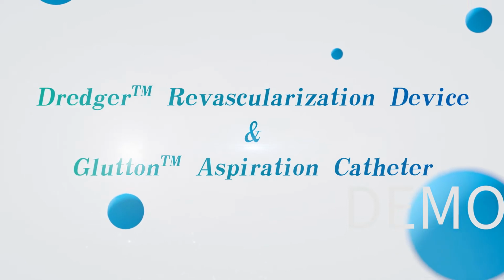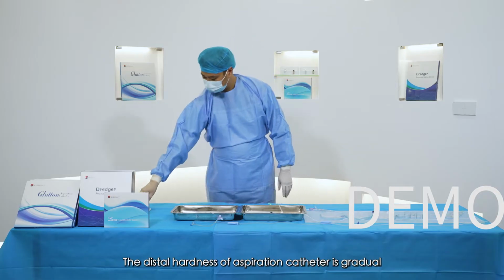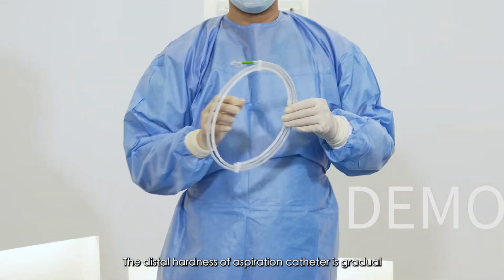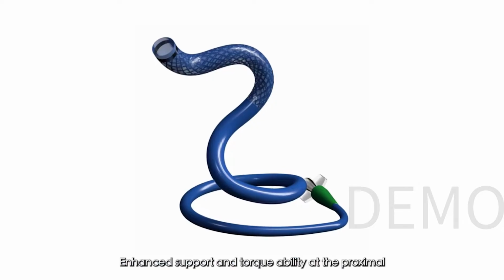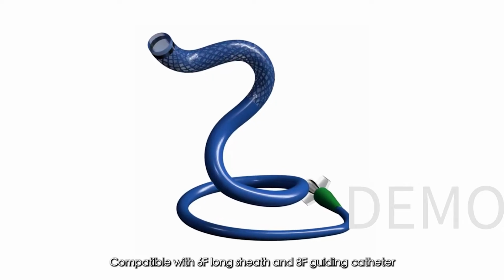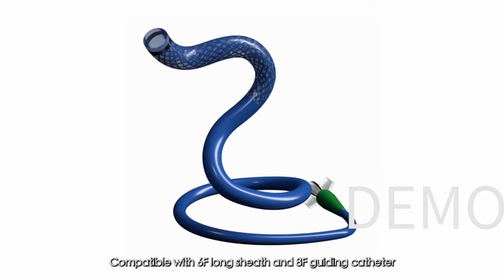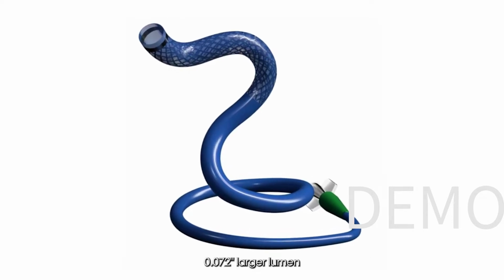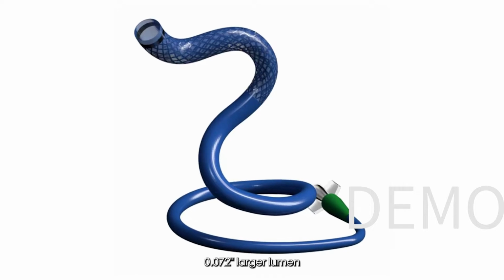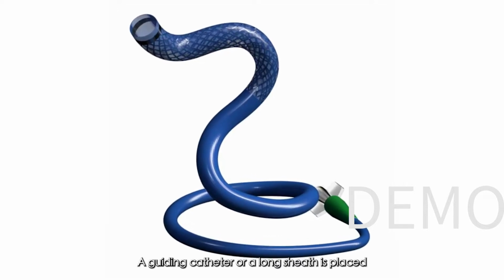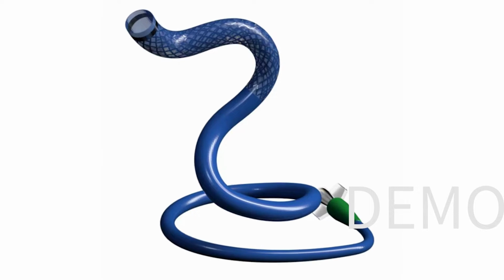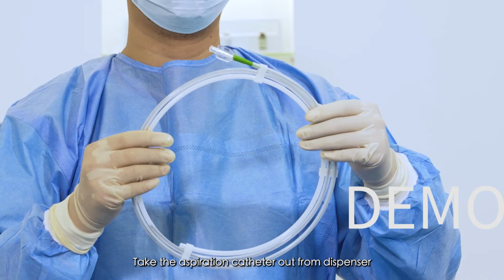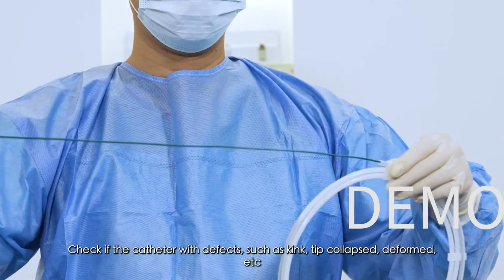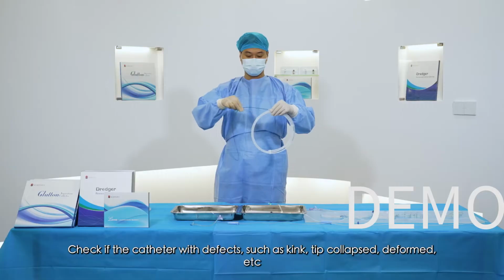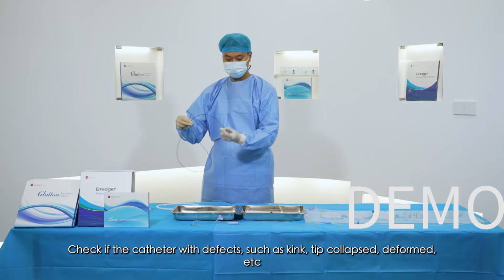The distal hardness of the aspiration catheter is gradual, with enhanced support and torqueability at the proximal end, compatible with a 6F long sheath and 8F guiding catheter. It has a 0.072 larger lumen. A guiding catheter or a long sheath is placed. Take the aspiration catheter out from the dispenser. Check if the catheter has defects such as kink, tip collapse, deformation, etc.